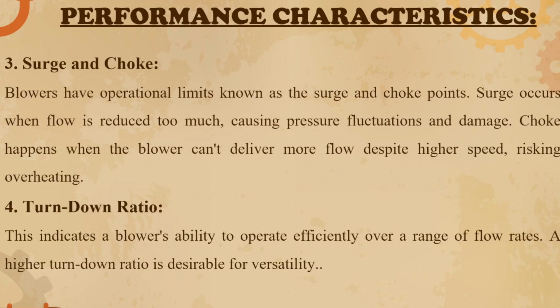Third characteristic is the surge and choke. Blowers have operational limits known as the surge and choke points. Surge occurs when flow is reduced too much, causing pressure fluctuations and damage. Choke, on the other hand, happens when the blower cannot deliver more flow despite higher speed, risking overheating. Another characteristic is the turn-down ratio. This indicates a blower's ability to operate efficiently over a range of flow rates. A higher turn-down ratio is desirable for versatility.